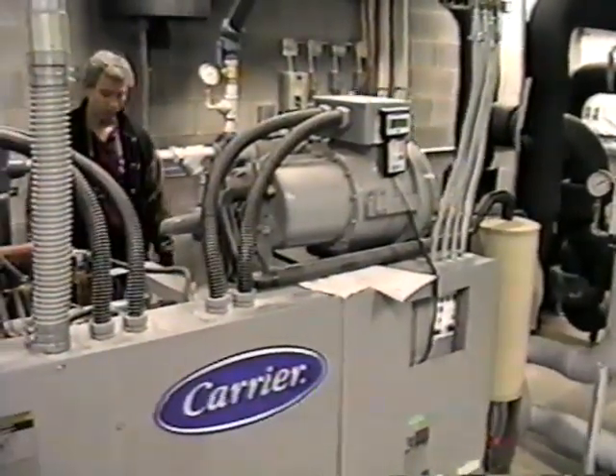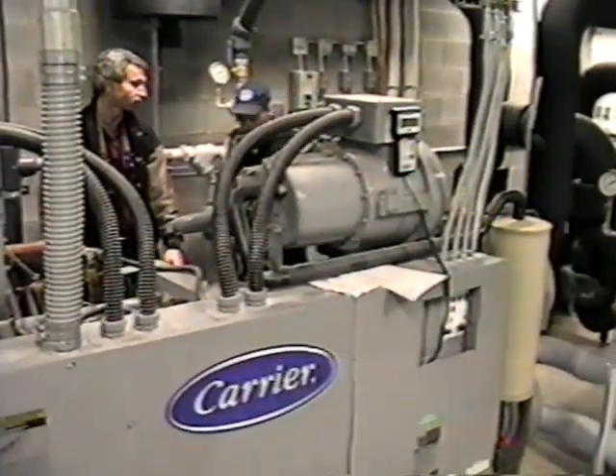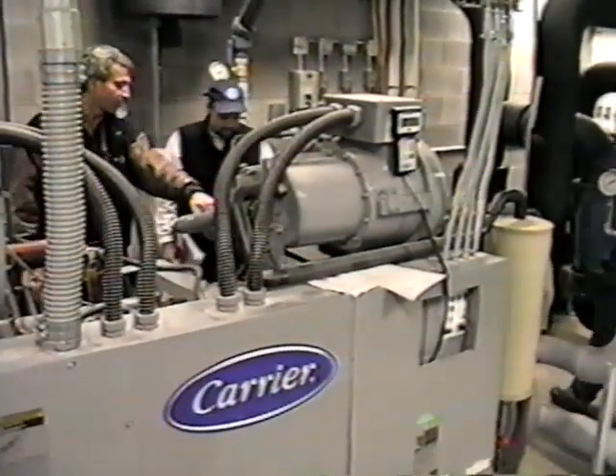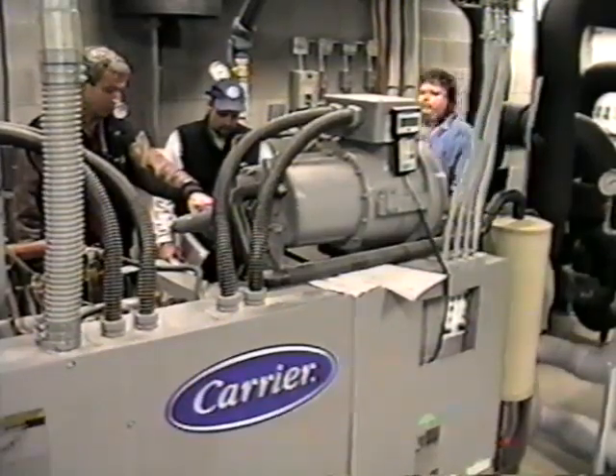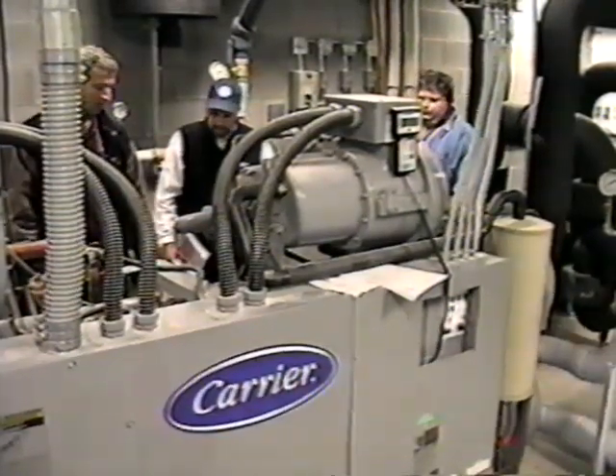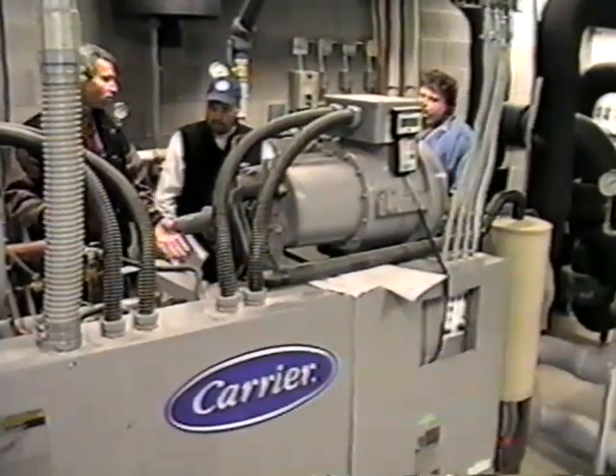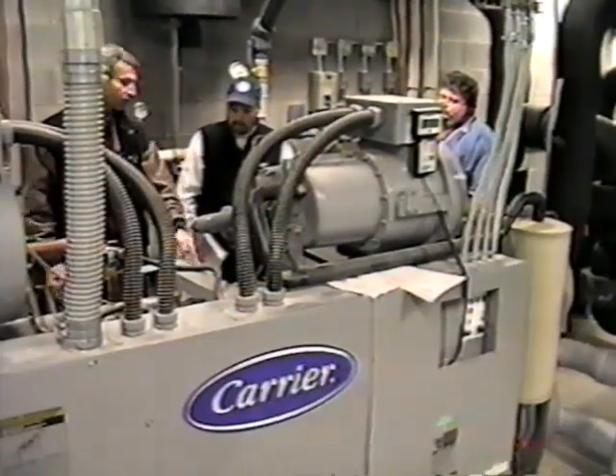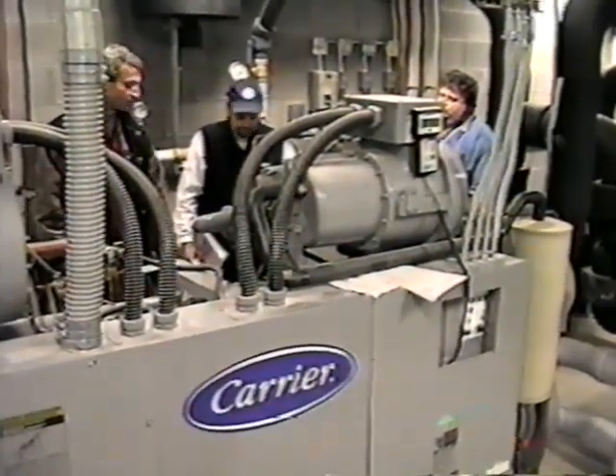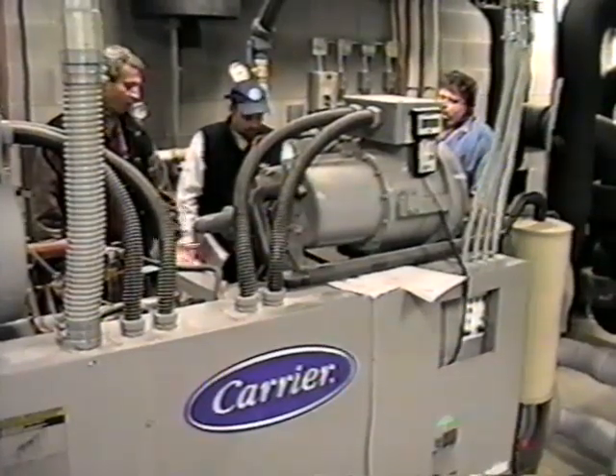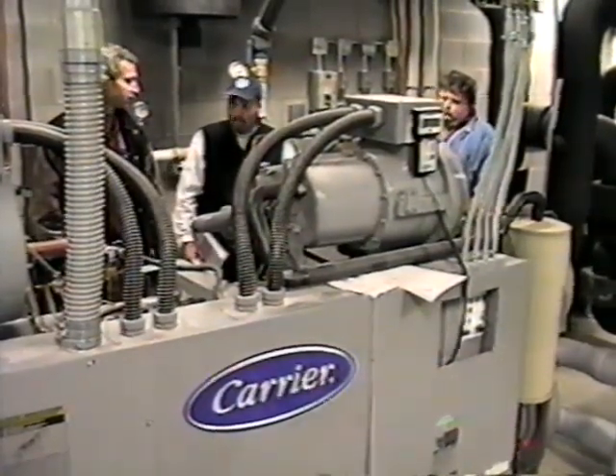I have an oil pump. This oil pump does start prior to the compressor starting, so you may hear it just before the compressor starts. If for some reason you were running exceptionally cold water, this may cycle on to try to maintain that oil pressure. But for the most part, with your control, you shouldn't see that happening.